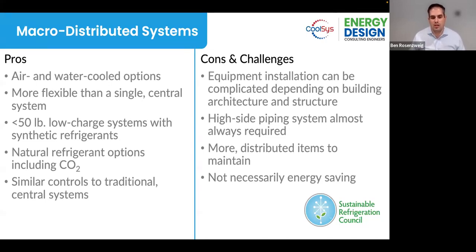Some of the challenges or downsides might be that equipment installation can be complicated depending on the building architecture and structure. The high side piping system almost is always required, meaning you have a remote condenser that you have to pipe the refrigerant to, which could lead to a larger refrigerant volume, more distributed items to maintain, and it's not necessarily energy saving over a central system depending on the design.